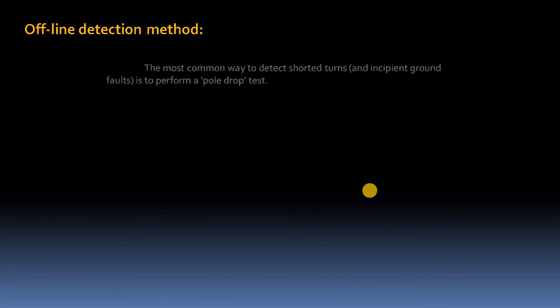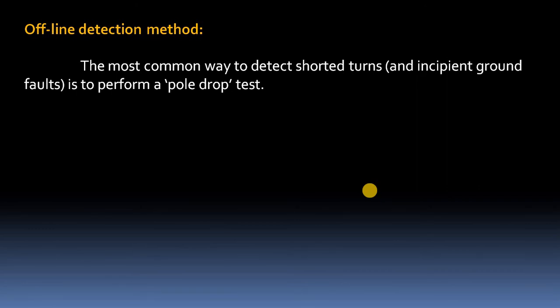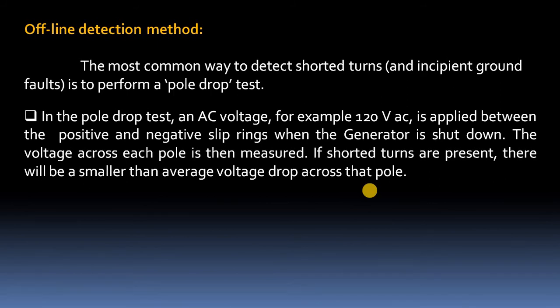In the offline detection method, the pole drop test is very simple and easy. The common way to detect shorted turns is to perform a pole drop test. In the pole drop test, we apply an AC voltage to the rotor winding at the slip rings and measure the voltage across each pole. If any pole has a voltage drop less than the average voltage, that pole has shorted turns.